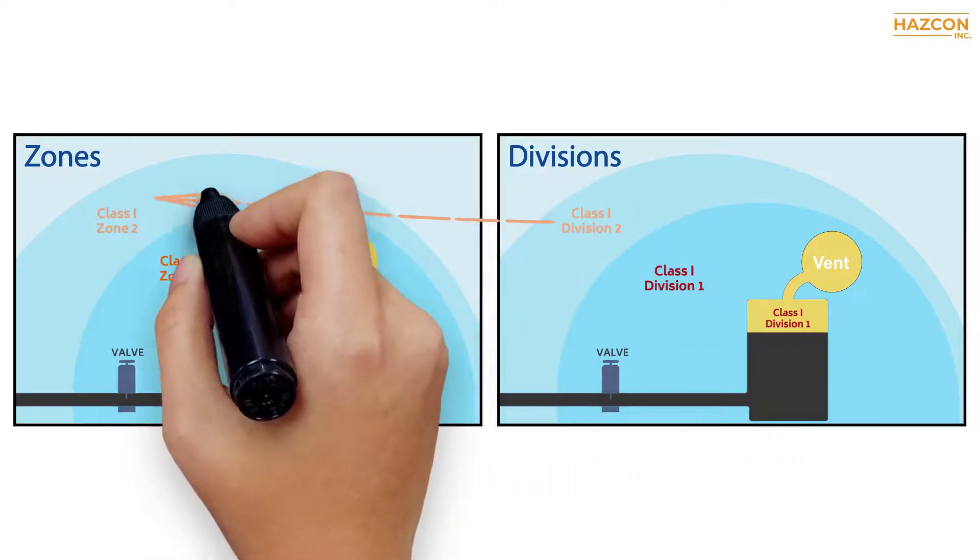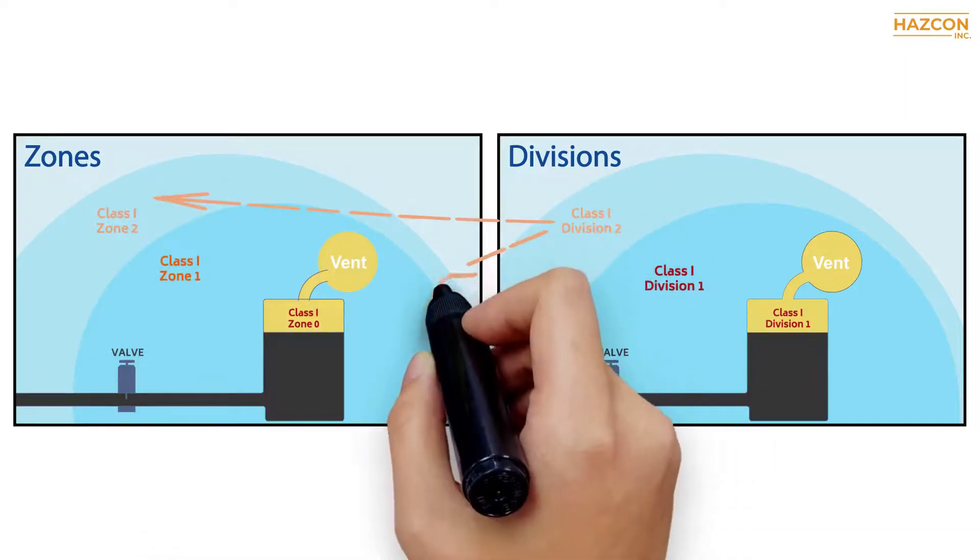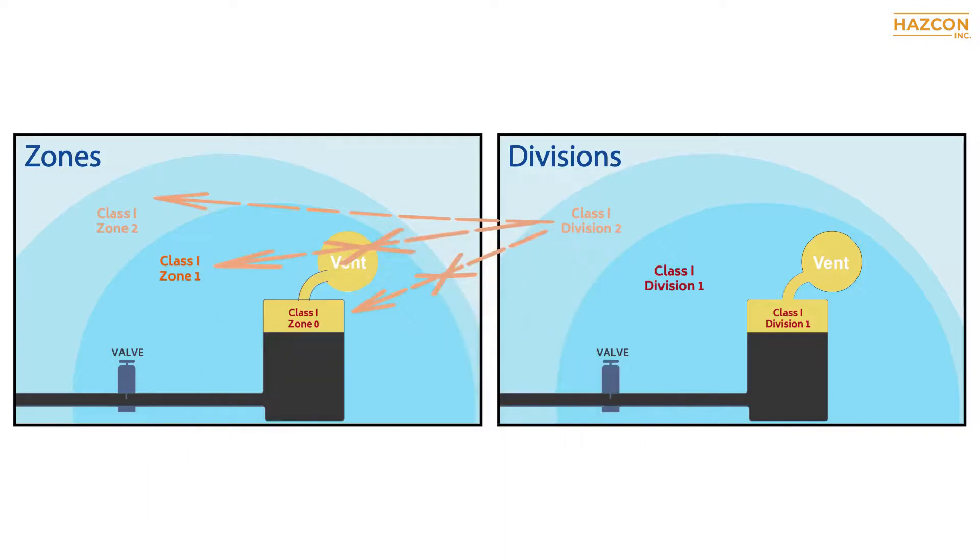Class 1 Division 2 products may be installed in zone 2, but may not be installed in zone 0 or zone 1. Class 1 Division 2 products may not be installed in class 1 Division 1 either.